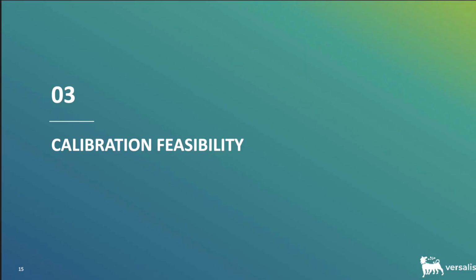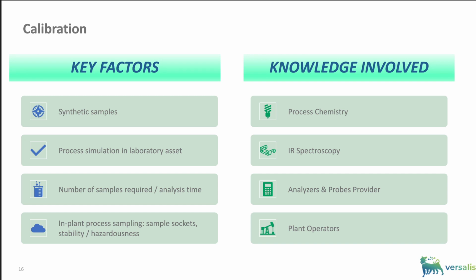Well, let's now consider the second operational cluster, the calibration. Calibration, the purpose of which is to enable quantitative information to be obtained from the spectrum, depends on the process stream considered and the variables to be determined. Different situations are possible. In the simple case, it may be possible to produce synthetic samples covering the entire range of expected calibration, while in other cases it is necessary to simulate the process in the laboratory. Depending on the number of variables and concentration range, the number of samples required, from a few dozen to over 100, must be assessed.